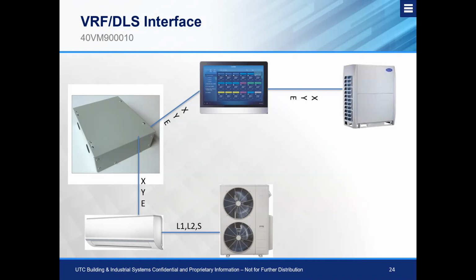So essentially what this ductless interface does is it takes the ductless protocol, sends it over to this ductless interface, and converts it into a protocol that the touchscreen controller can interpret and display, just like we have with the Carrier VRF system. It's important to note that for this interface, this gray box, you must have one per ductless indoor unit. So you can't have 5 indoor units reporting back to one box. One per indoor unit, but we do have the ability to have that centralized monitoring and control, not only of the VRF system now, but of the ductless system. Now, for commercial projects, that certainly is a great advantage.